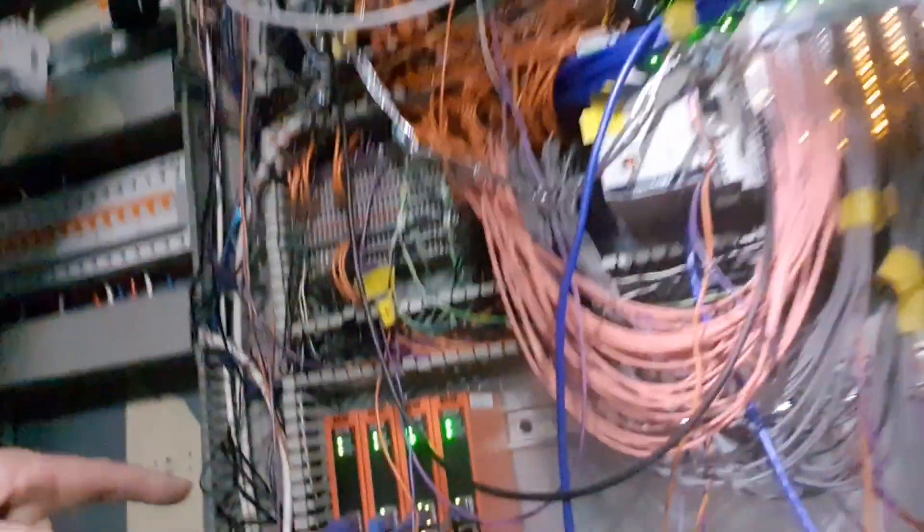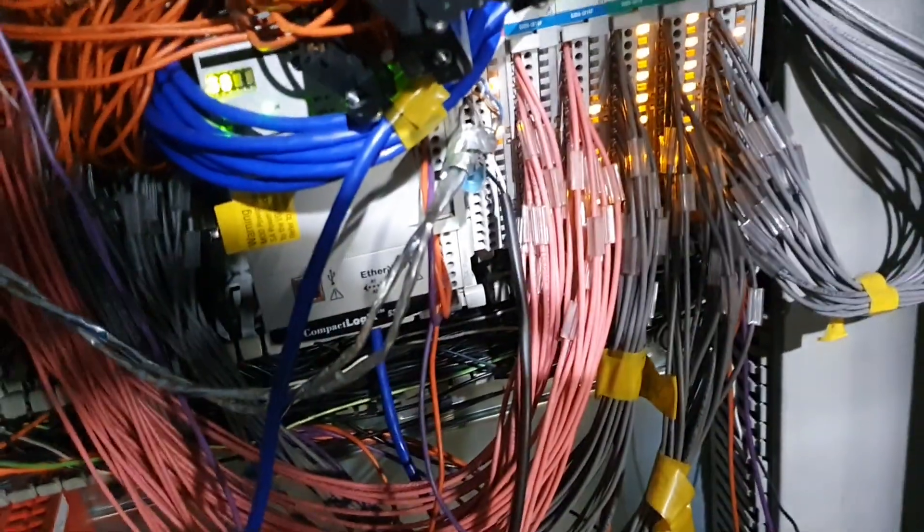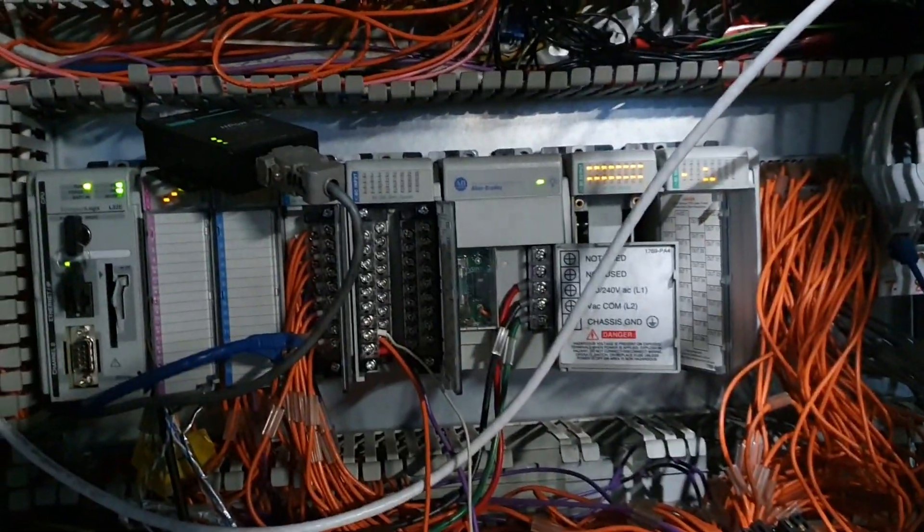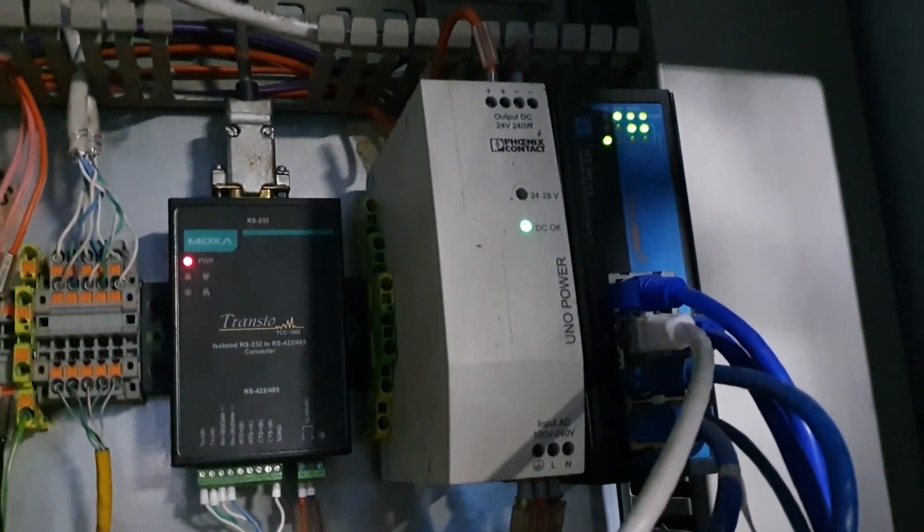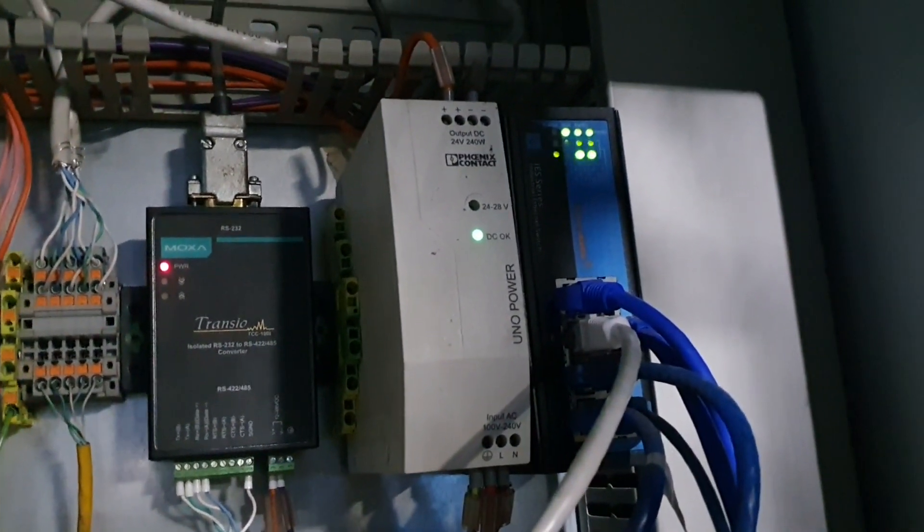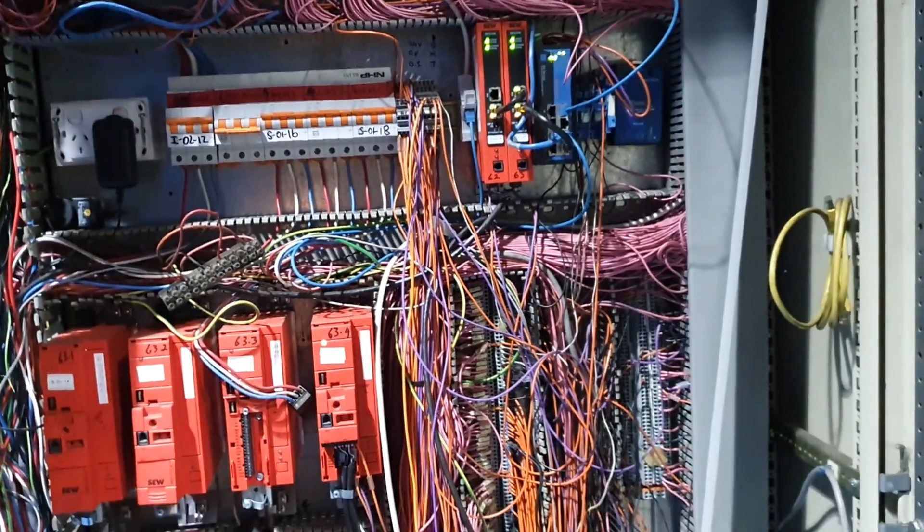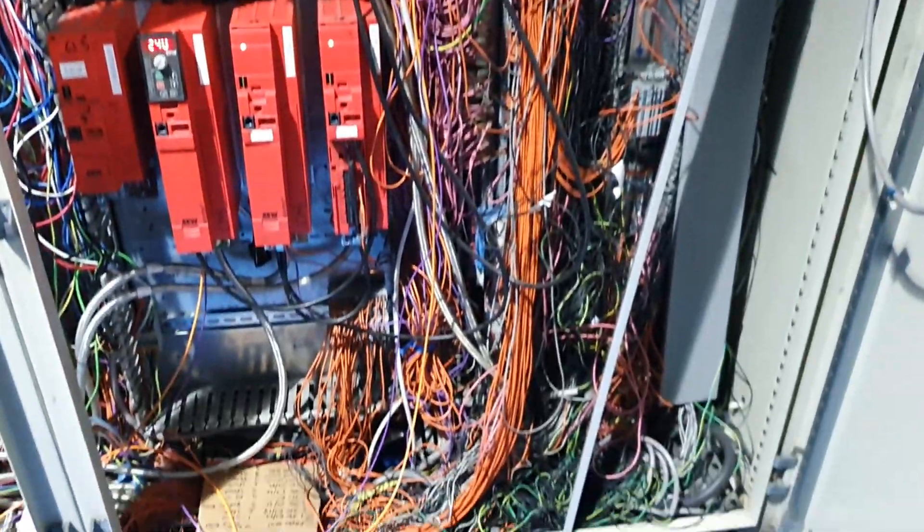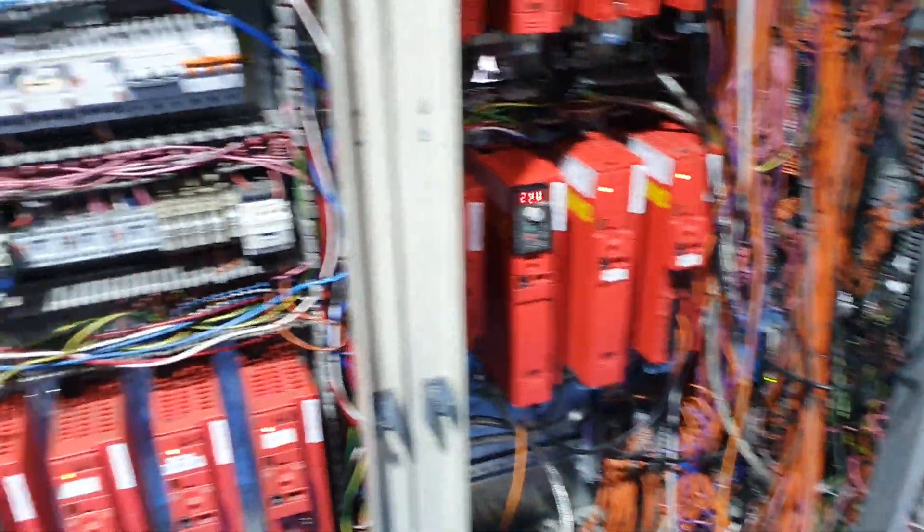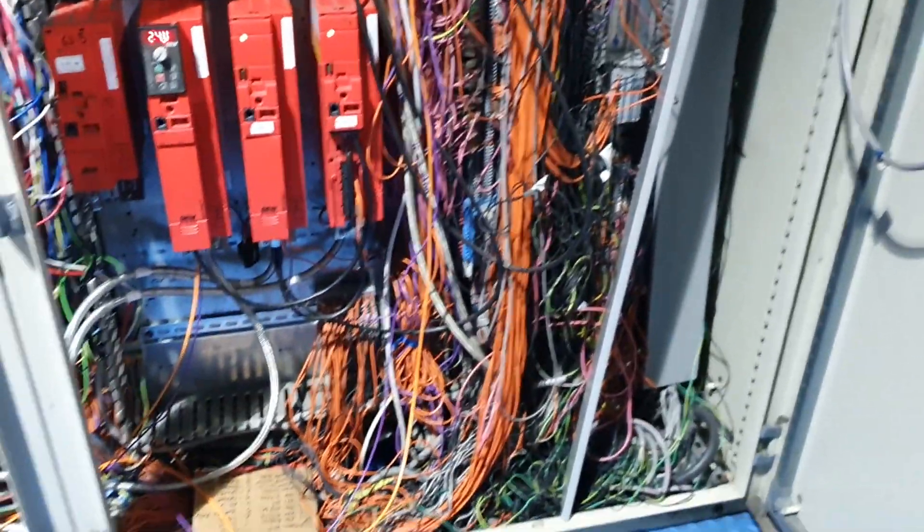Lights on. All righty. Turn it back on. All the green lights are on. Nice. These are SEW drive gateways. We've got the gateways here. These control a lot of the motors in this place. Got a PLC there. PLC there. That was losing sync with everything. And this power supply here was the thing that I originally thought was the issue. Now this is a classic example of what you don't want to see when you walk into fault finding a control panel.